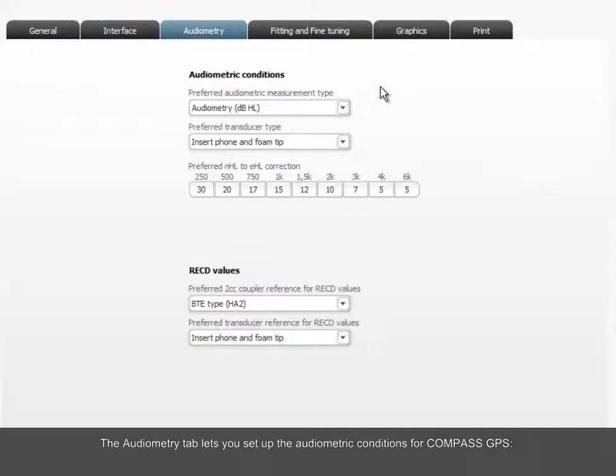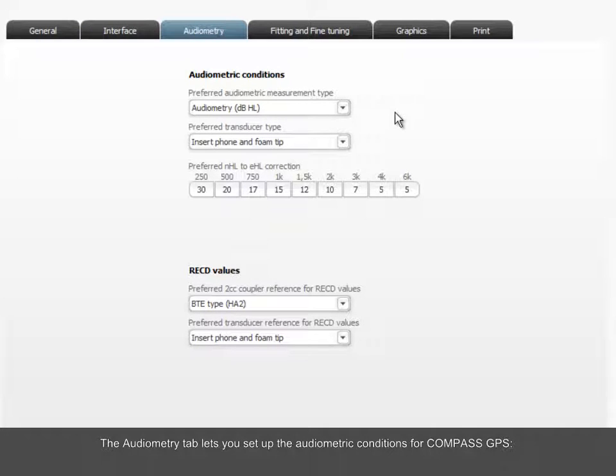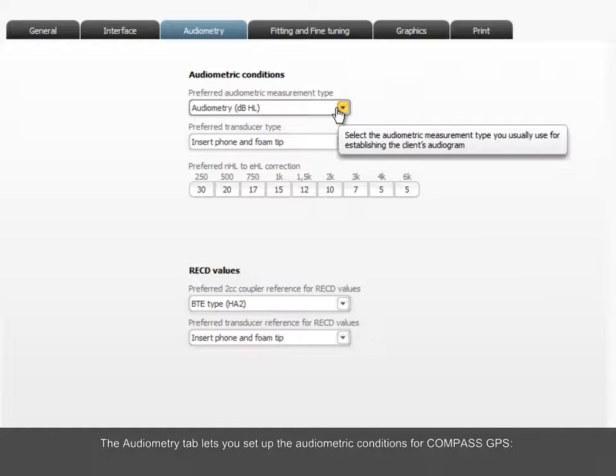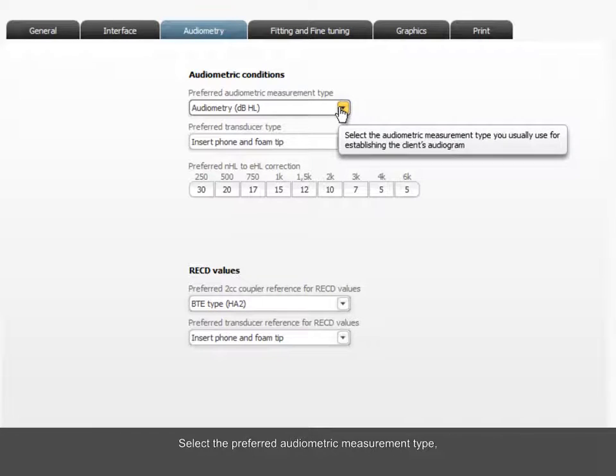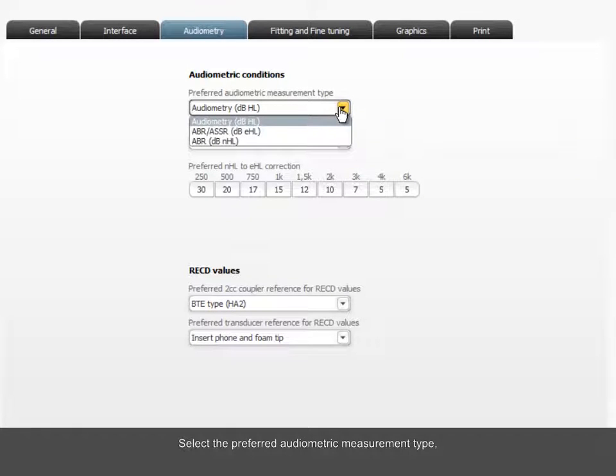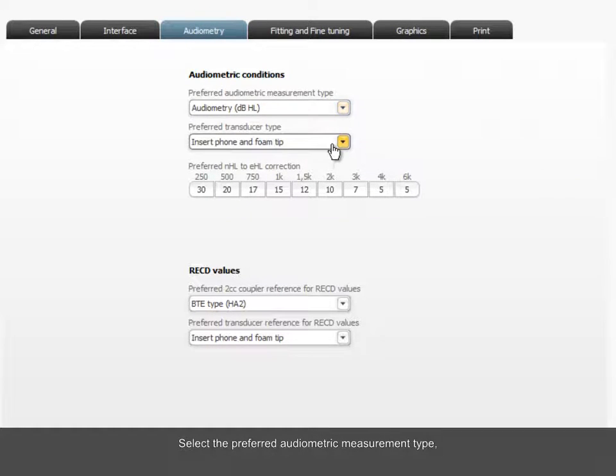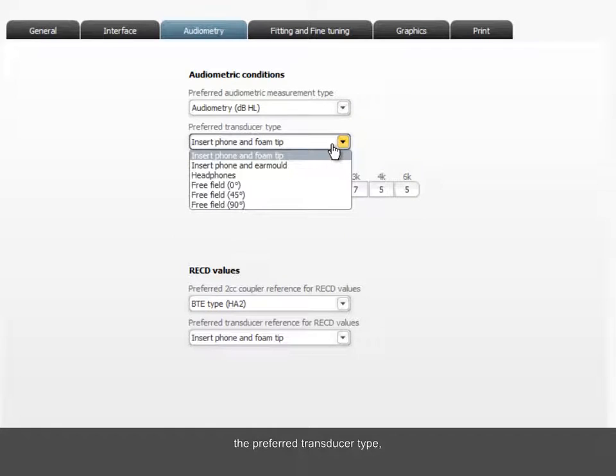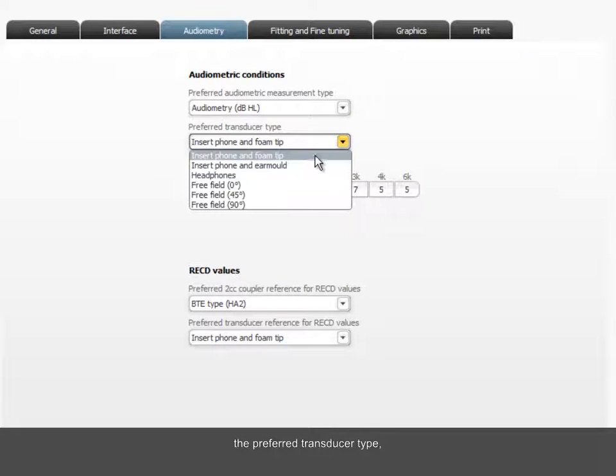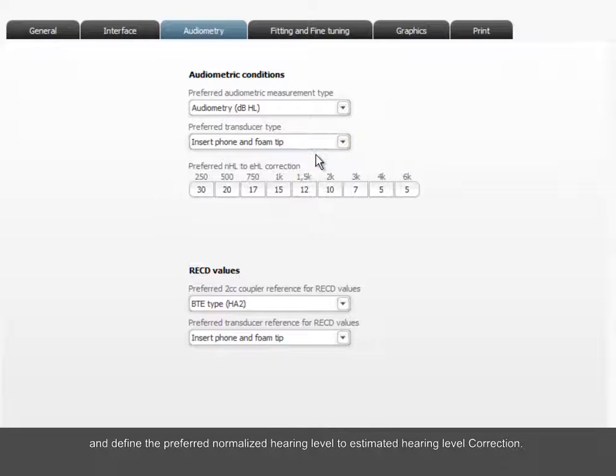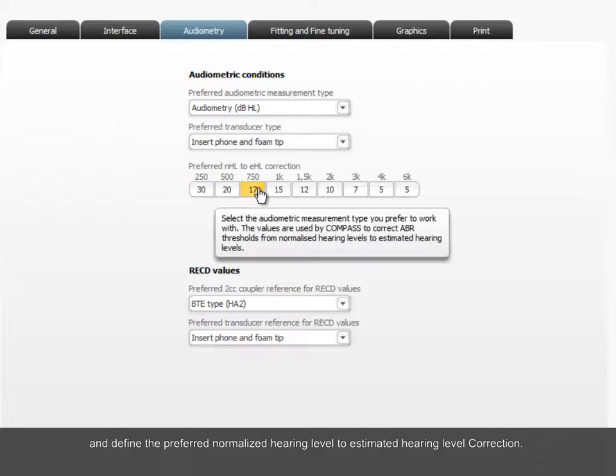The Audiometry tab lets you set up the audiometric conditions for Compass GPS. Select the preferred audiometric measurement type, the preferred transducer type, and define the preferred normalized hearing level to estimated hearing level correction.